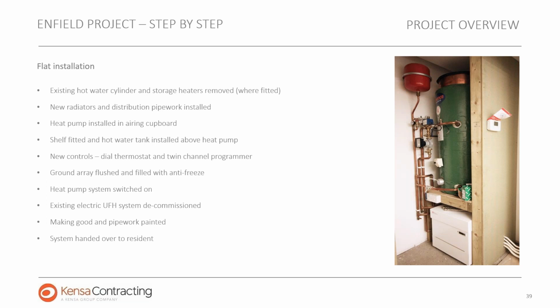We were removing existing hot water cylinders, showing them the new radiators and distribution of pipework, and how the heat pump is installed into the airing cupboards. There's a shelf fitted and the hot water tank is installed above the heat pump. We showed them the new controls, thermostats, and thermostatic radiator controls, so they can control their heating system in individual rooms.